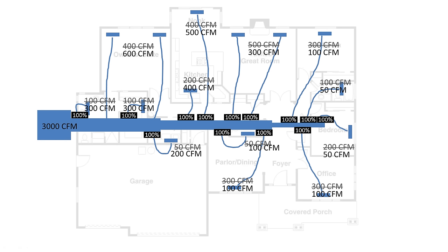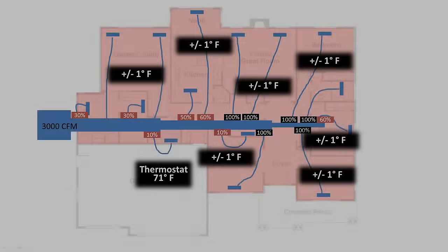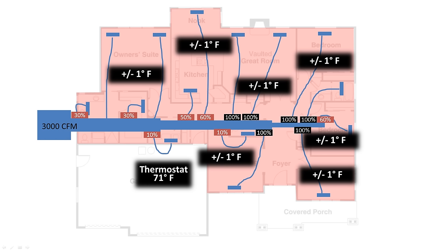That's why you end up with hot spots and cold spots. Instead of getting maybe 400 CFM to the master bedroom, it gets too much air — like 600 CFM. The opposite end of the house, where a room may need 200 CFM, may only be getting 50. This is why you have hot spots and cold spots in your house.